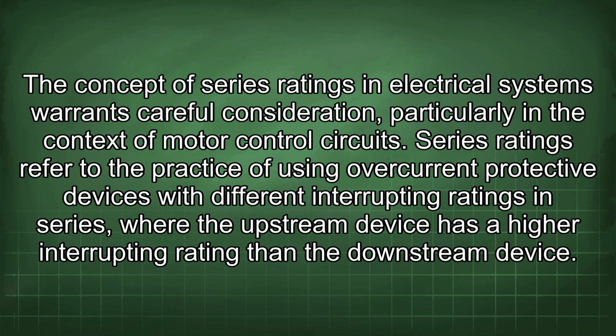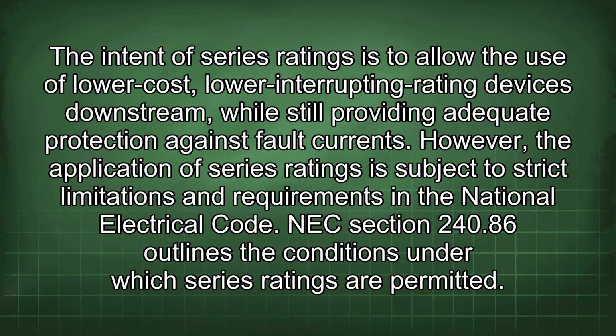Series ratings refer to the practice of using overcurrent protective devices with different interrupting ratings in series, where the upstream device has a higher interrupting rating than the downstream device. The intent of series ratings is to allow the use of lower-cost, lower interrupting rating devices downstream, while still providing adequate protection against fault currents.